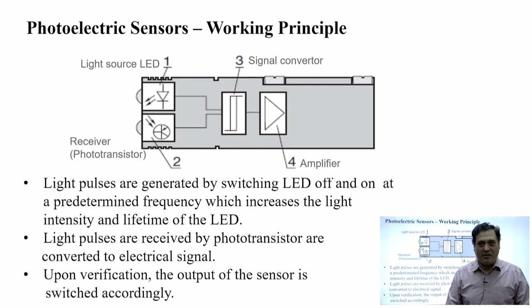Now, one of the most important concepts of photoelectric sensors is that we all know a white color object has the maximum reflectivity compared to a dark color object. A white object, such as Kodak white paper, has a maximum reflectivity of 90%. That means, if light falls on a white color object, it will reflect back almost 90% of the light to the sensor. Whereas a jet black object, which has the lowest reflectivity of 6 to 7%, will reflect only 6 to 7% of the light. So, photoelectric sensors are designed keeping in mind the maximum reflectivity, which we get with Kodak white paper, which is used for printing photos. These sensors are designed keeping white Kodak paper as the reference target material, which has the maximum reflectivity of 90%.